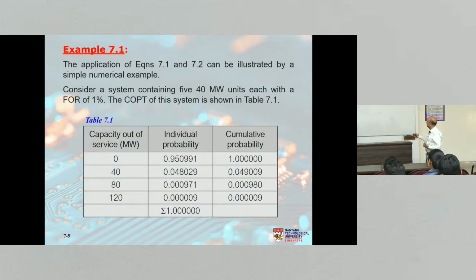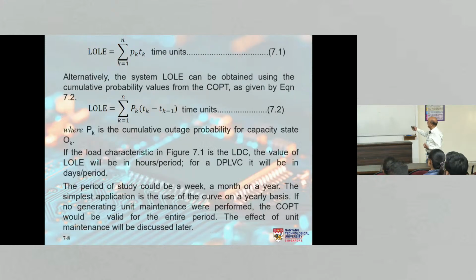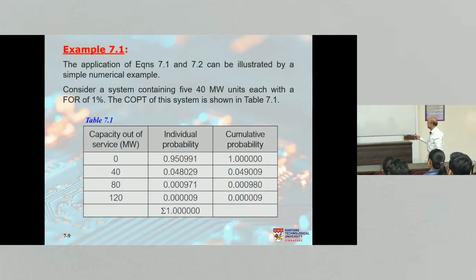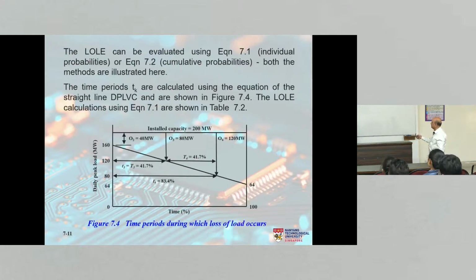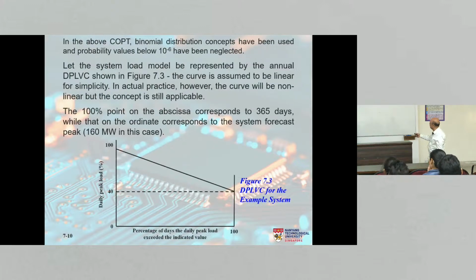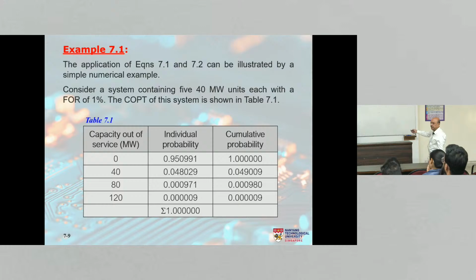That equation, if I use that equation, P(k), T(k), the time unit is 0, right? So that first thing, when there is no outage, no generator is out, that is T(k) is 0, right? Then the next outage is 40 megawatt, right? How many states are there? We just use this table, right? 0, 40, 80, 120. We are stopping at 120, right? So to make things easier. So 40 megawatt out, I know the probability. I also know the cumulative probability, but I'll come to cumulative later. For now, I'm just using the state probability.